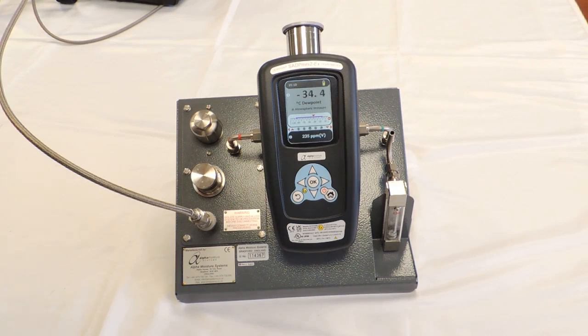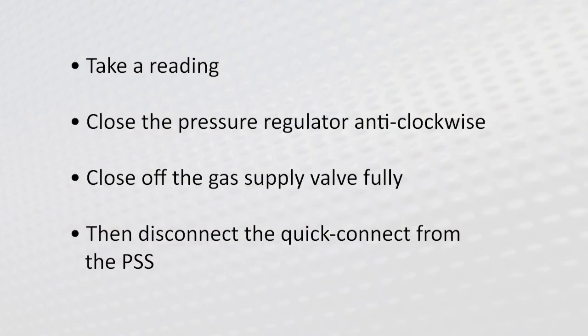You'll see that the dew point has reached equilibrium. At this point you can take a reading and you can close off the pressure regulator by closing it anti-clockwise, then close off the gas supply valve fully and then you can disconnect the quick connect from the PSS.